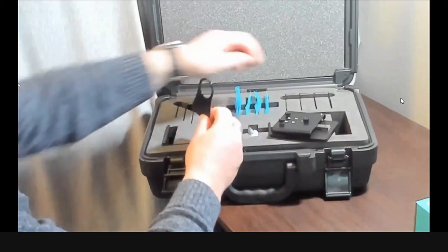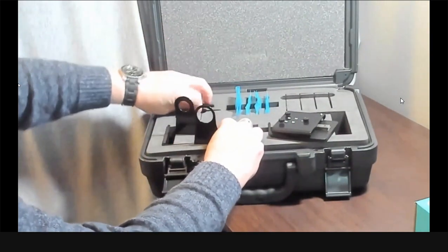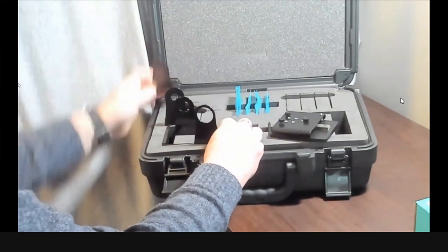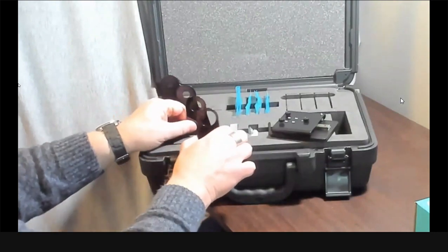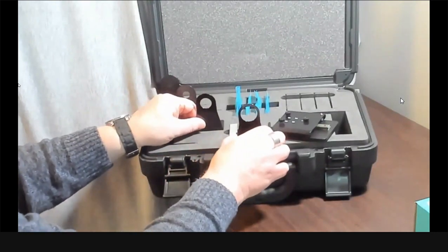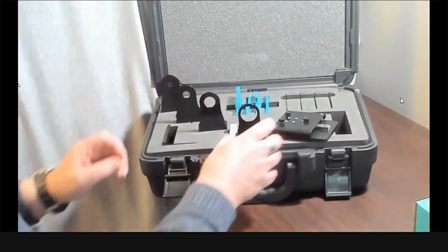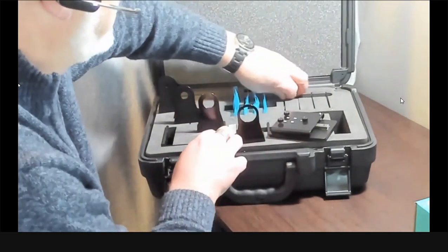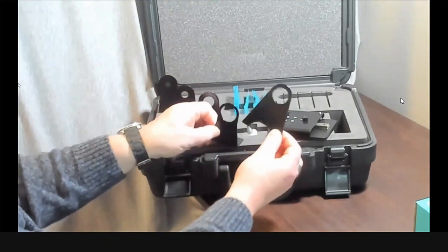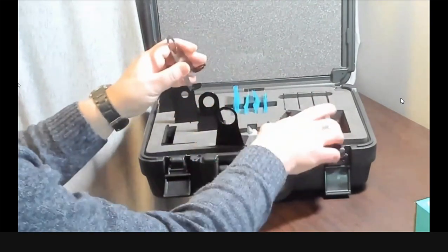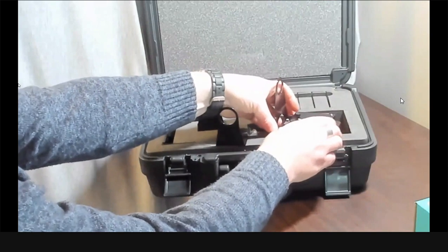This is where you position it depending on your aperture plate. We have the 25, 10, 17, and 3.5 mm, depending on your device configuration. We are the only spectro, I think, that can accommodate different sizes in terms of transmission measurement. The 3.5 again is optional, so you have to purchase it separately.